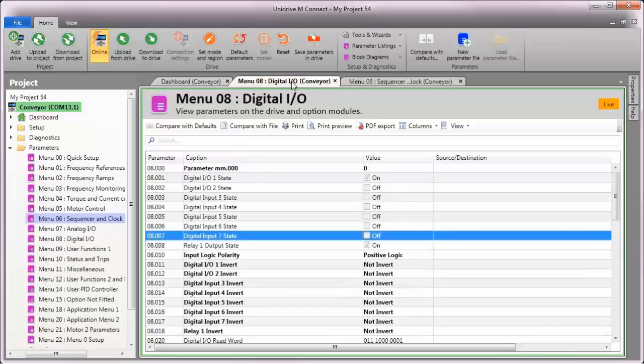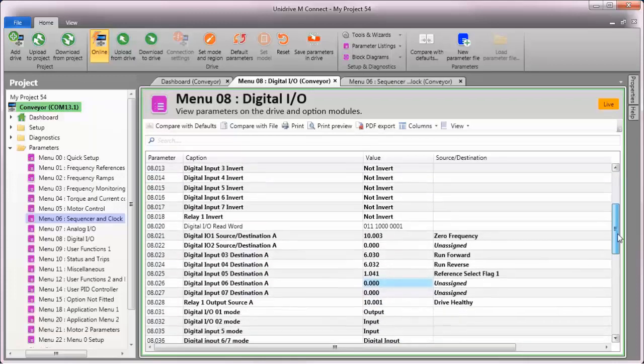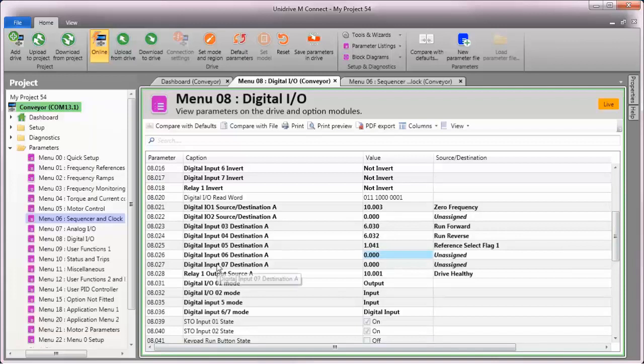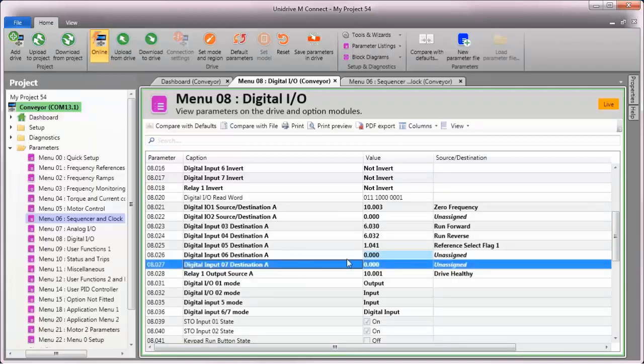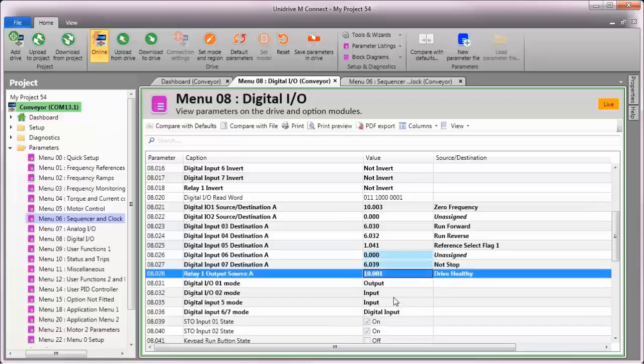Let's go back to menu 8 now and assign the destination not stop to digital input 7. To do that, I'll double click on menu 8, parameter 27, and assign it to have the destination menu 6, parameter 39, or not stop.